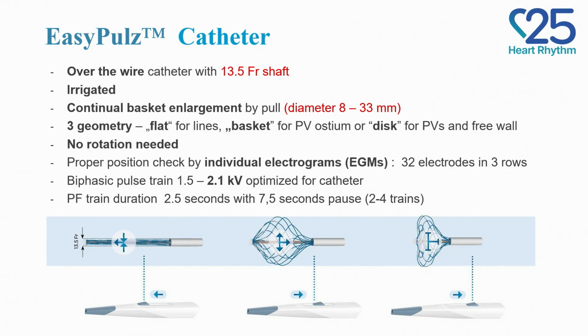multiple electrodes, like 32 electrodes, in 3 rows, and the diameter is 33 millimeters at maximum. And actually, it's very interesting that even in the collapsed fashion, which is 8 millimeters in diameter, I can show you this collapsed catheter, you are able to deliver the pulse. This is very important, that actually there is no arcing, no other funky shape. You really don't get any arcing, as we know from other pentaspline catheters and maybe others, okay?